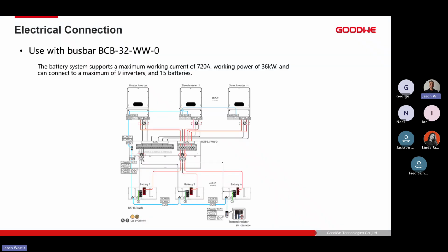As mentioned in the parallel slides, the battery does need to be connected to a bus bar. The recommendation is to be connected to a bus bar when paralleling more than one battery. GoodWe has its own bus bar, the BCB32-WW-0. We have a smaller one, which is a 22. It's just the physical size of the bus bar itself. However, the working current maximum goes up to 720 amps, a working power of 36 kilowatts.